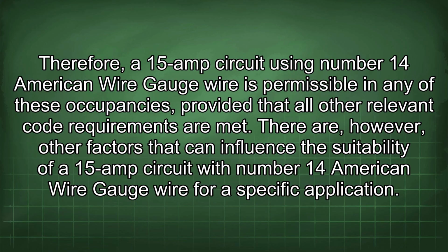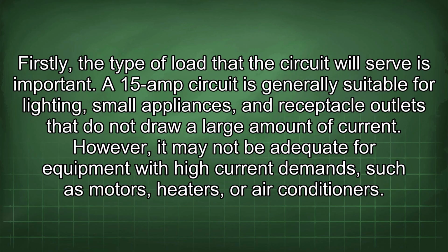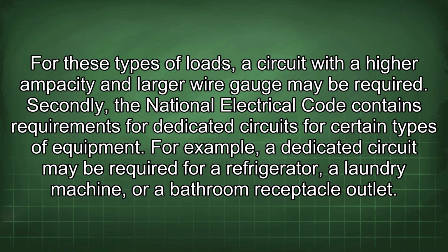There are, however, other factors that can influence the suitability of a 15 amp circuit with number 14 American wire gauge wire for a specific application. Firstly, the type of load that the circuit will serve is important. A 15 amp circuit is generally suitable for lighting, small appliances, and receptacle outlets that do not draw a large amount of current. However, it may not be adequate for equipment with high current demands, such as motors, heaters, or air conditioners. For these types of loads, a circuit with a higher ampacity and larger wire gauge may be required.